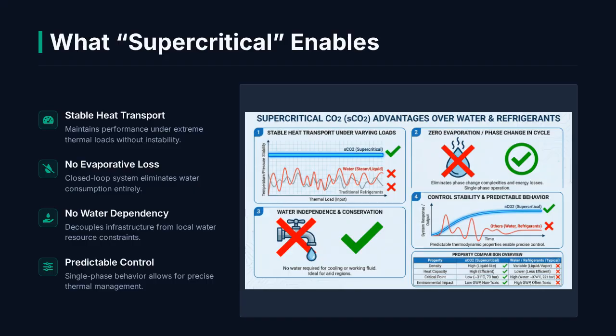Unlike water or refrigerants that rely on phase change, supercritical CO₂ enables stable, single-phase heat transport even under extreme thermal flux, eliminating evaporation losses and water dependency. The fluid remains in a consistent state, allowing for precise thermal management and predictable system behavior across varying computational loads.